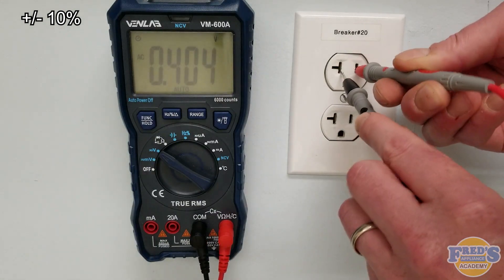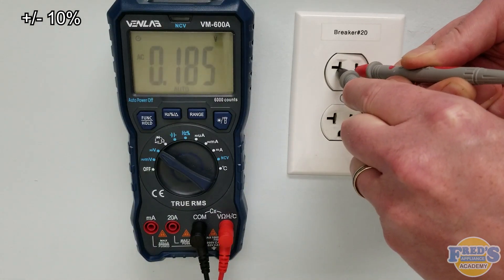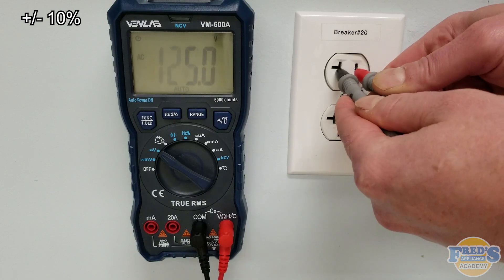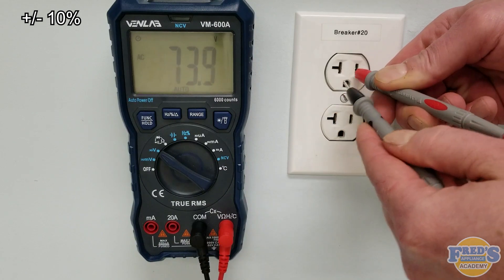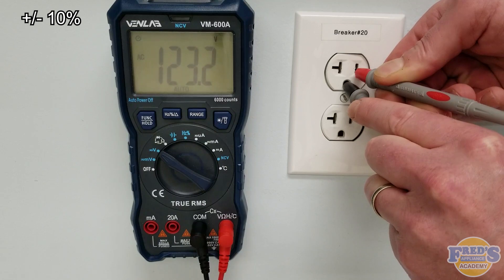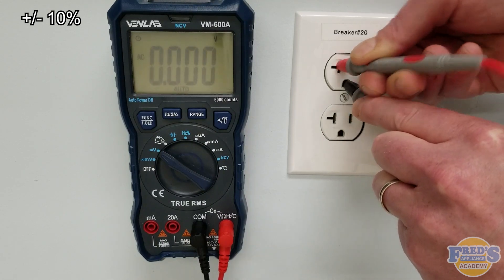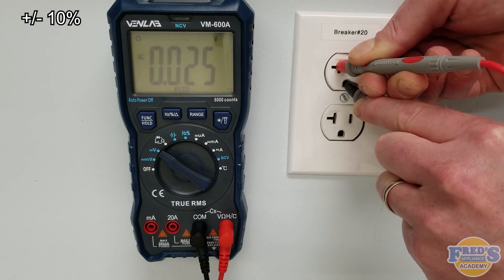We're going to go ahead and put our meter leads in hot and then neutral where we should be getting 120 volts. Next, remove it from the neutral and go to ground where we get 120, and then we go from neutral to ground where we should get nothing.